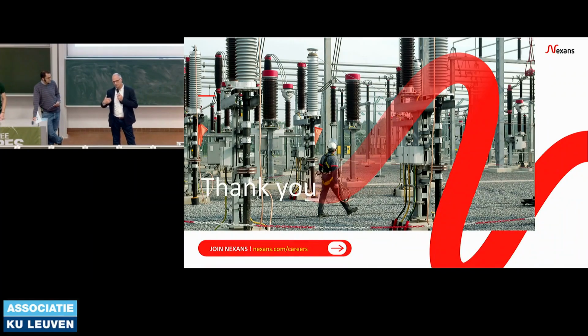Most of the time, our main task in terms of testing will just be to check that the main insulation is in good shape, the outer jacket is in good shape, that we do not have any permutation of phases, that for example, if we have surge voltage limiters, they are correctly installed and in good shape as well. So this is where our task will finish.